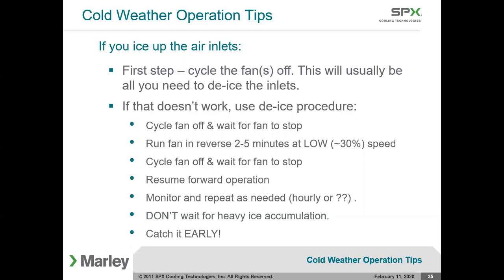If that doesn't work, then we should go through a de-ice procedure, something like this: turn the fans off and wait for the rotation to stop, run the fan in reverse for 2 to 5 minutes at low speed, approximately 30%, cycle the fan off, wait for it to stop. Hopefully the ice is now melted and we can resume operation. What this does is it pulls the cold air in the top of the fan. It goes the opposite way, from the inside to the out through the fill. So the air has warmed up significantly by interacting with the water that's falling down across the fill. And so when that air gets to the ice, it's warm enough to melt it. Resume operation, monitor and repeat as needed. Don't let it get too bad. It's better to catch it early.